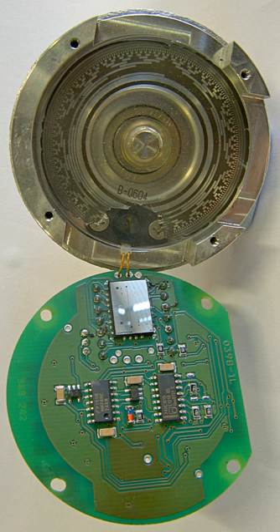On-axis magnetic: this technology typically uses a specially magnetized two-pole neodymium magnet attached to the motor shaft. Because it can be fixed to the end of the shaft, it can work with motors that only have one shaft extending out of the motor body. The accuracy can vary from a few degrees to under 1 degree. Resolutions can be as low as 1 degree or as high as 0.09 degree, 4000 CPR, counts per revolution. Poorly designed internal interpolation can cause output jitter, but this can be overcome with internal sample averaging.